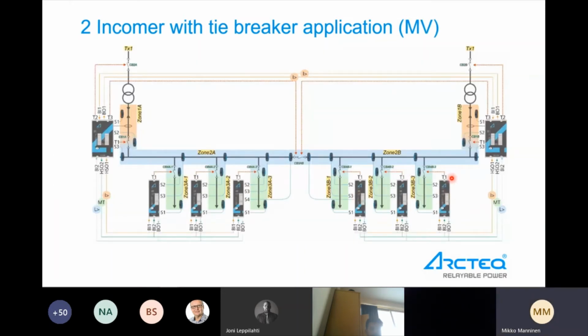And then very similar to incomer with tie breaker application for the medium voltage. I don't know, medium voltage is a term which is not used in all the countries, and probably there is only low voltage and high voltage. But in Finland and some parts of Europe, medium voltage is the term when you go over 1000 volts and you are less than 45 kilovolts. But medium voltage or high voltage, however you like to call it.